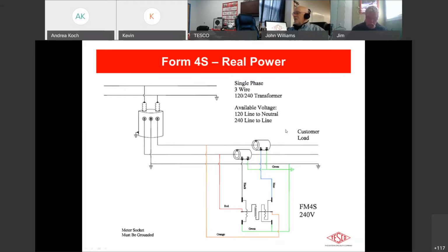Yeah, so down here in Texas, they use a lot of the 4S meters on smaller restaurants that may have air conditioning load. It's only for single phase instead of 3-phase. And then we also have a lot of large ranch houses that are more than the 320 amp meter, actually higher than 400 amp on these large ranches. So they always go to the 4S meter on these.